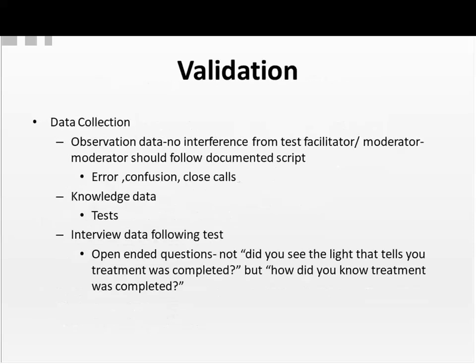Okay, let's look at a validation study itself. Data collection. You're having observation data. You're collecting data on the observation. There should be no interference from the test facilitator. There's also knowledge data, where you conduct tests on the participant's knowledge of the device, of using the device, and information about the device. There should be interview data collected following the test.